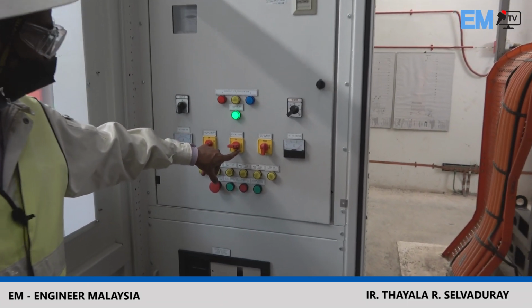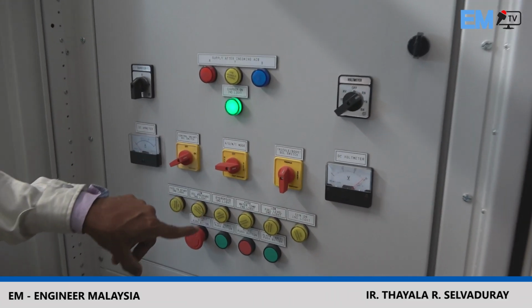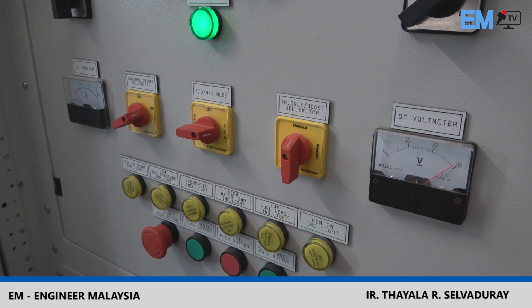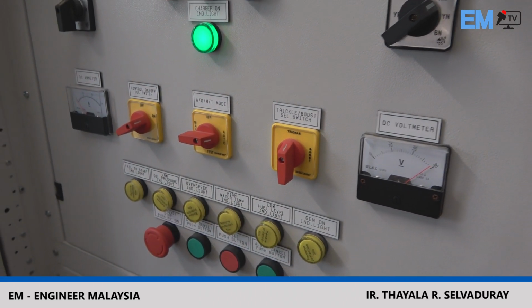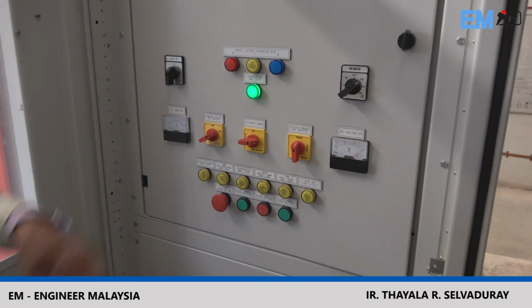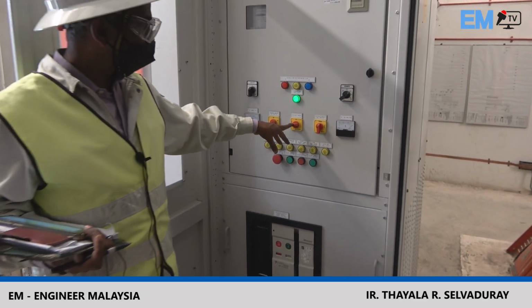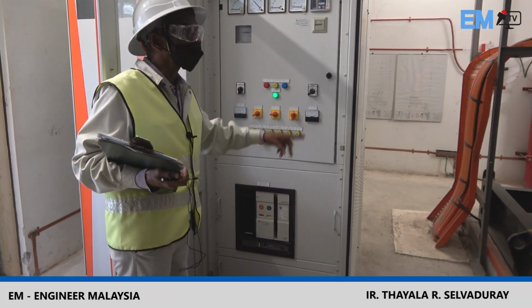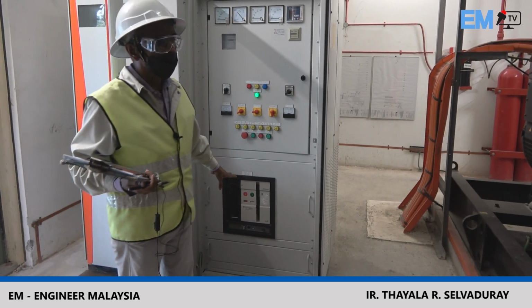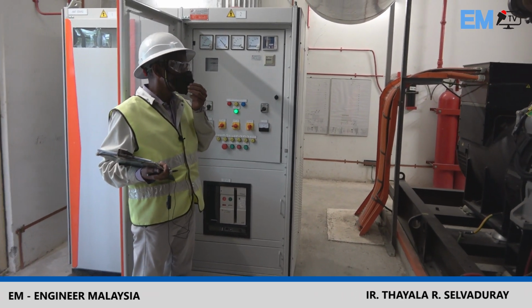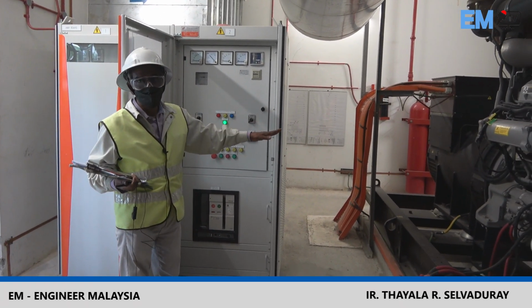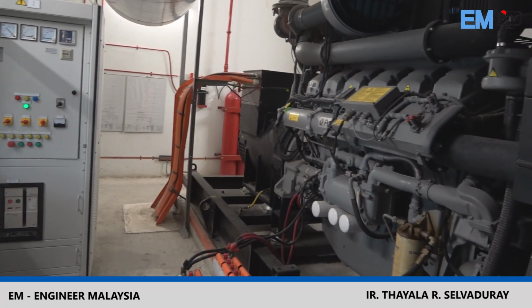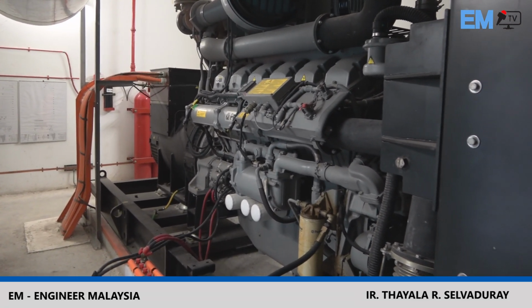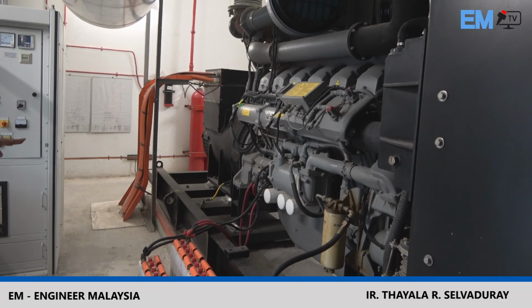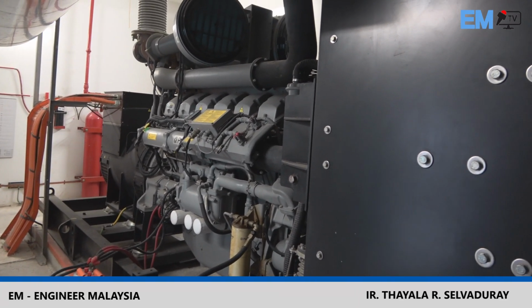So when it's set on auto, whenever there is a power dip after a certain amount of time, for example maybe 10 seconds or more, 30 seconds, depending on how you want to set it, immediately this thing will cut in and the generator will start. And the moment the signal for the generator starts, within 5 to 10 seconds the generator is at full speed, and immediately the whole supply comes in. So in other words, an interruption will be only about a maximum of 10 seconds, right? It all depends how you want to set it, but it's about 10 seconds.